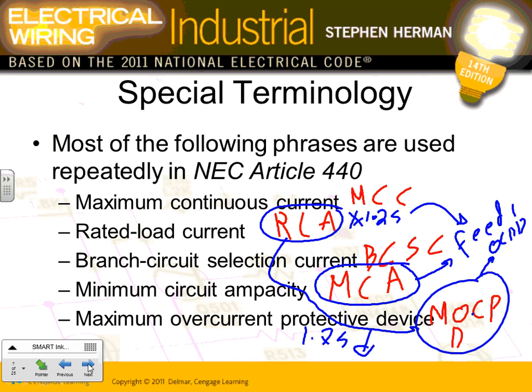Branch circuit selection current, guys, because HVAC equipment has controls and fans and compressors all in one big box, sometimes they add all the amps and put them as branch circuit selection current or rated amps. Whichever is larger, you use to size your equipment. So any of these on the nameplate, you can size your equipment. But Jeff, don't cry too much, because you can have the minimum circuit ampacity and maximum protection device printed right on your chiller. So all you have to do is provide a feeder with the same size based on the amps, no calculation of minimum circuit and overcurrent device. Any comments, guys? Any questions?